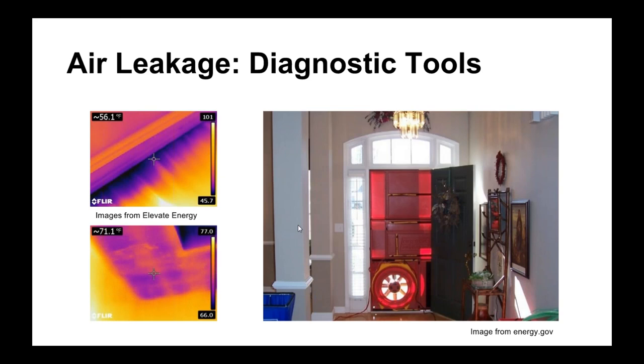When you're first going to a single-family home, there are a couple of diagnostic tools you can use. The first one is using an infrared camera. When you're using an IR camera, you're looking for a temperature difference, which represents the heat flow through a building's flaws. If there's a gap between baseboards and the outside, or not enough insulation, you can usually see that through the camera if there's enough of a temperature difference between inside and outside — so if it's a cold day.